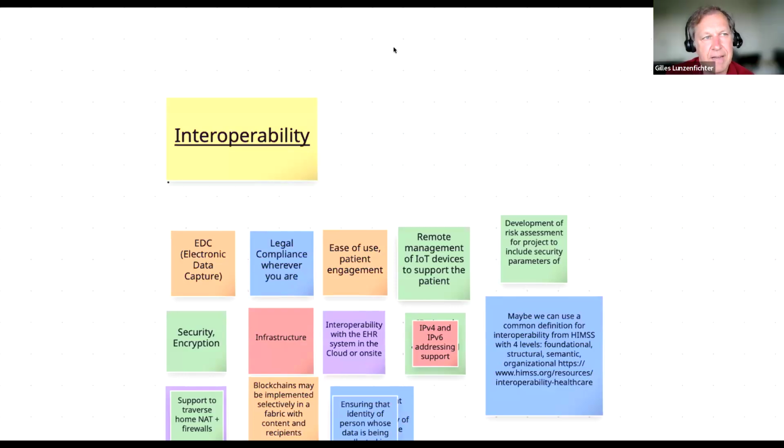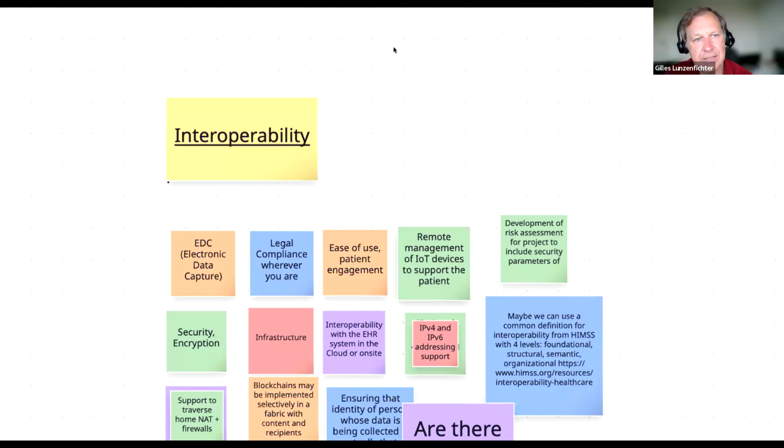If I tie back to the question of whether we are sure it's the person using the device: we had use cases in heart insufficiency where it's critical to monitor the spike in weight increase, because this is the first sign of decompensation by the patient. But the weight scale is usually in a bathroom, where you might have the cat, a piece of luggage, or a grandchild who jumps on it because it's funny. Then on the telemonitoring side, suddenly some stupid data points come in. We had such a situation in a real deployment of telemonitoring of heart insufficiency patients.